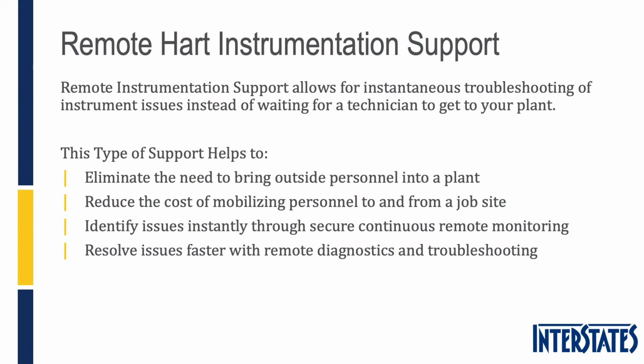Next, I want to talk to you about another E&I service that can be provided, mainly instrumentation. This service is unique in the fact that it can actually fix issues inside of a plant without a person actually being at the plant. This is remote instrumentation support. What this involves is remoting into the network of a facility, connecting through a Hart card inside of the PLC, and then ultimately connecting to a Hart device through that card, talking to that device, troubleshooting that device and configuring that device.